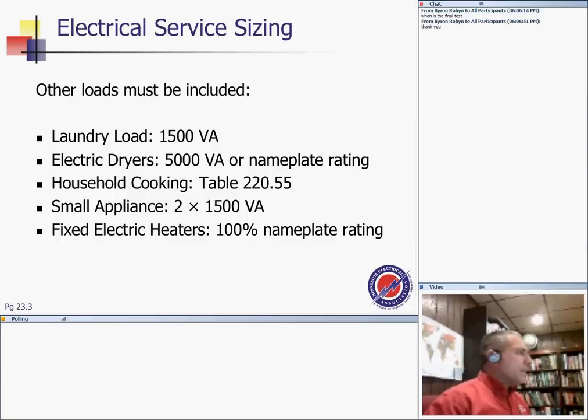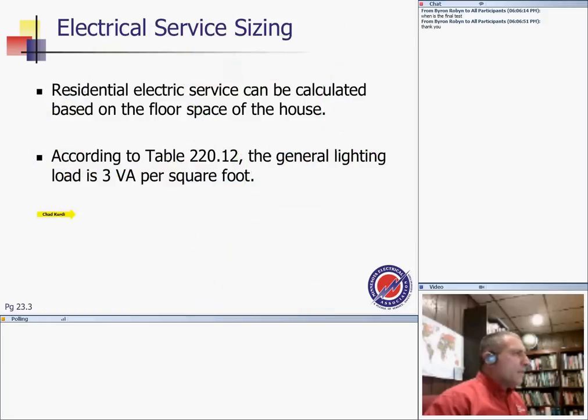The first thing we do is basic code book, and I'll show you guys the Excel sheet has all the requirements in any code book that they use. First, guys, let me erase this one so you can see the first requirement. The first requirement from this table 220.12 gives you the general lighting loads, which based on this table, is 3 volt-amps per square foot. And my friends, only for residential.